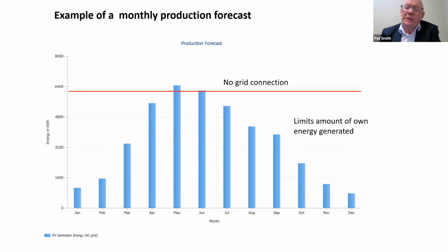One good thing with solar is that it's very modular and you can take a staged approach. You don't have to do it all on day one, and it's easy to expand. But without a grid connection, you're trying to size the system so that at peak generation you're below your base load. So that limits the percentage of your own energy that you can displace.